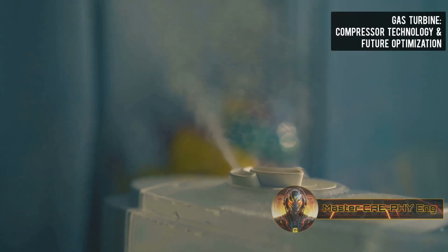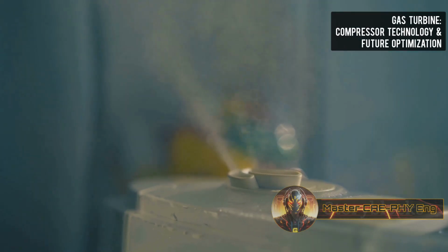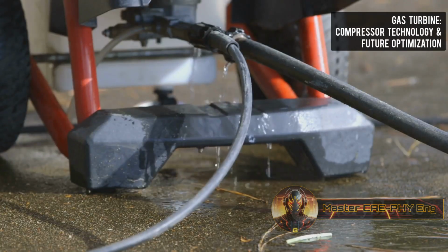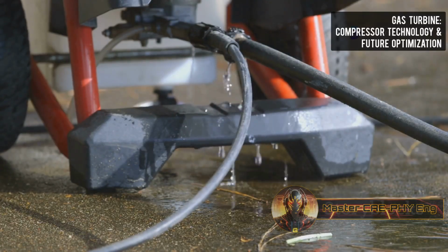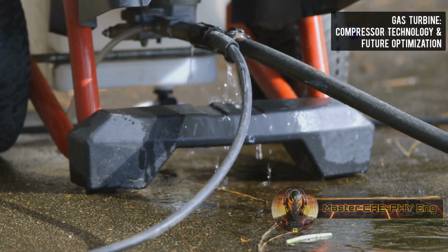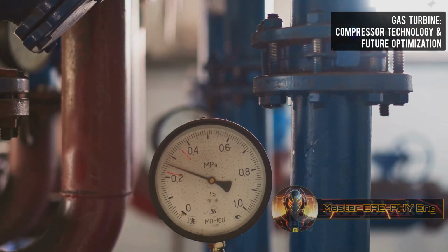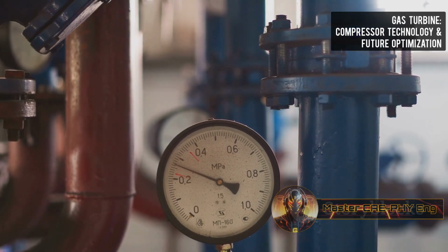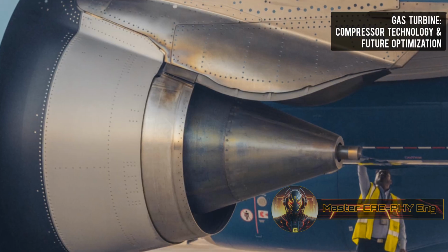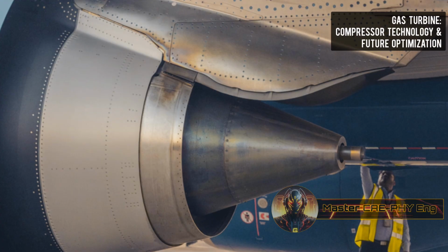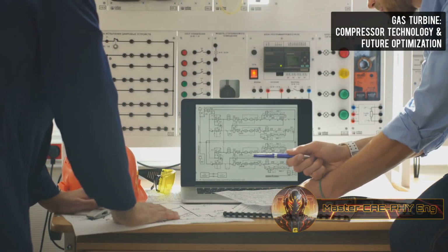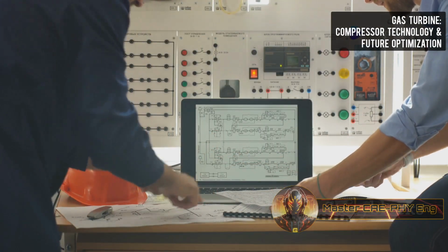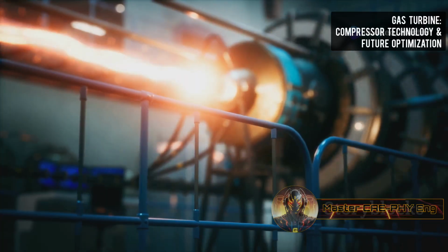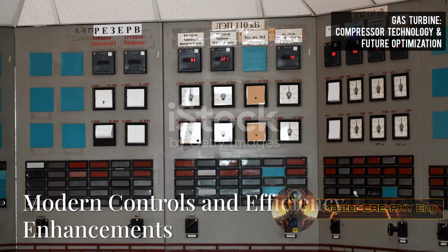Moisturizing inlet air can enhance performance by cooling and increasing mass flow. Techniques like high-pressure fogging or direct water injection provide intercooling effects. This reduces compression work, increasing pressure ratio and efficiency. Careful control of water injection avoids blade erosion. Managing inlet air conditions optimizes gas turbine operation. This is especially valuable for stationary power generation units.